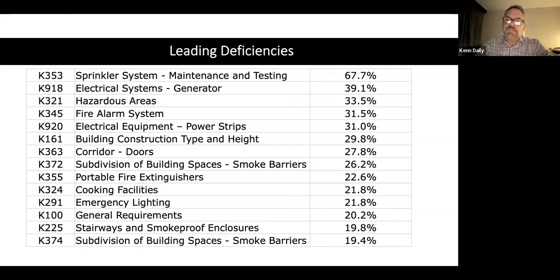So leading deficiencies across Pennsylvania, and I'll just give you a clue, there's a website that CMS posts all of its deficiency information on, and for you all and most across the country, the number one citation in most states is going to be sprinkler system testing, inspection testing, and maintenance, or as I refer to it, ITM. And that's because, as you'll see, there's a lot of items that show up in a single K tag, 353, which is the catch-all for all the sprinkler quarterlies and annuals and internal inspections and those types of things. And then you'll see in your state generator is the K918, essential electrical, and we'll talk about that.